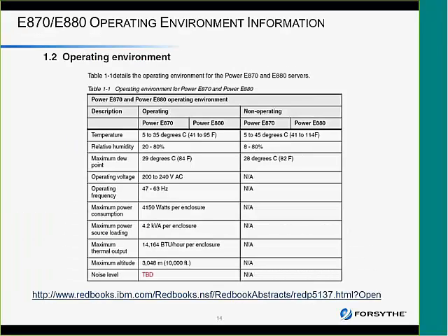Now for the E870 and E880, their operating environment is a lot higher than people expected. Each enclosure is 4.2 kVA. So right there, if you have a 30 amp PDU, which is rated at 4.8 kVA, you can see that you can only connect one E870 or E880 enclosure per PDU. So if you end up with a two-node 870, you're going to need 4 PDUs just to support the 870, and you could probably throw the HMC on there as well, but that's it, because that's going to be 8.4 kVA plus the HMC and so on.